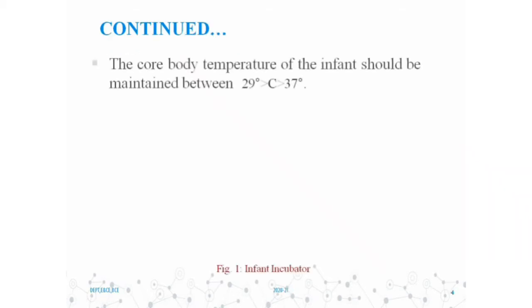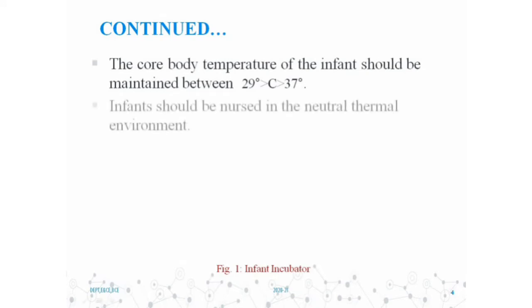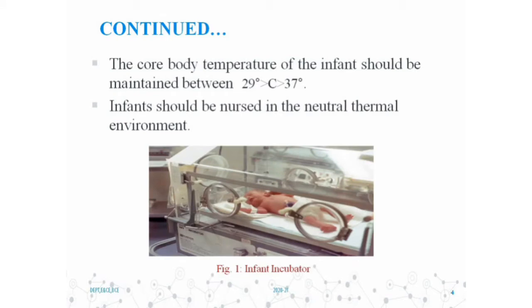The core body temperature of the infant should be maintained between 29 to 37 degrees Celsius, and the infant should be nursed in a neutral thermal environment. This is the picture of the infant incubator.